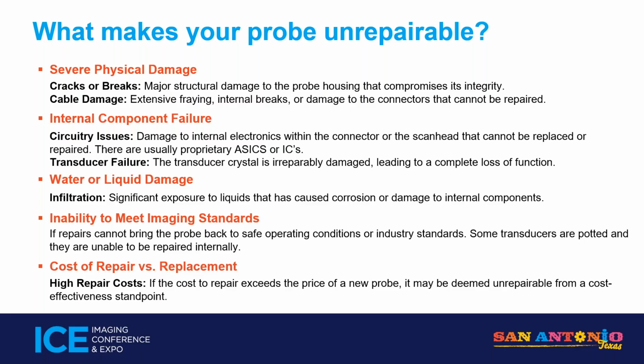Pretty much anything else is repairable, unless they're potted probes. Potted means they put epoxy over the electronics, so you can't get to them to repair, even if you know it's a bad cap - you can't reach it because it's covered in epoxy. A lot of manufacturers make potted probes, and you take the casing off and realize it's not repairable. If they just didn't do that, we could repair it. But a decision has to be made.